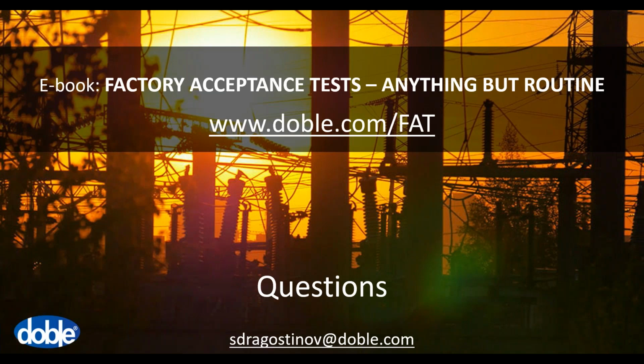Yes, I suppose, and potentially, if you're doing a PD measurement, you don't want the pumps running because they could increase the noise level. It will create a noisy environment, so it's not preferable. So whilst we're talking about PD, a couple of questions related to PD. What's the rejection level for a PD measurement? So I guess what's the pass-fail criteria? And related to that, can you pause the PD measurement and then continue again? So I guess they mean take the voltage down, do something, and then take the voltage back up again.